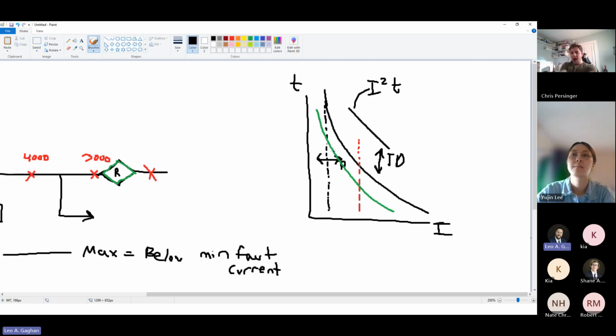But it's really up to you what you pick. If you picked 1.2, which was on the smaller end, maybe you've got to bump that time dial up a little bit more. If you picked 1.5, which is on the less sensitive side, maybe bump that time dial down a little bit. But it's usually up to you to make it work.